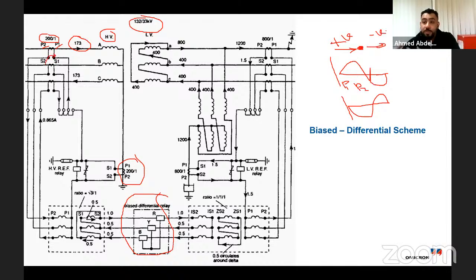This is to simplify the calculation. Then I need to calculate the resistance. I need to calculate the high impedance resistance to limit the voltage, or to generate a voltage which the bias differential protection needed. What else do I need? I need to do something which is called adaptation. Adaptation of the current in from the CT, because I have two different values.